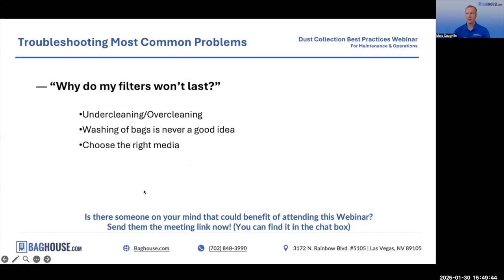Washing of bags. We run into this from time to time. There are people out there who offer the service of laundering filter bags. Sounds like a good deal to save money on bags. Problem is, specifically with felted filter media, which is most commonly used for filter bags, introducing water to the filter fabric will basically degrade it and break it down. Just like if you've ever had one of those old-fashioned felt hats, if you throw it in the laundry, it will not do well. It'll basically fall apart. Same thing happens with felted filter fabrics, like felted polyester and things like that.